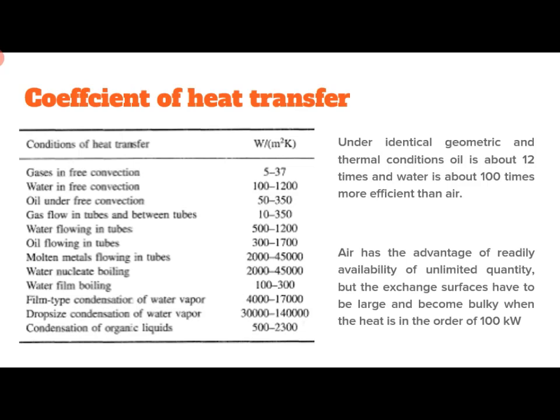The overall coefficient of heat transfer shows that under identical geometric and thermal conditions, oil is about 12 times and water is about 100 times more efficient than air. Various coefficients under different conditions of heat transfer are given, with ranges listed. Typically, oil is about 12 times more efficient than air and water is about 100 times more efficient than air.